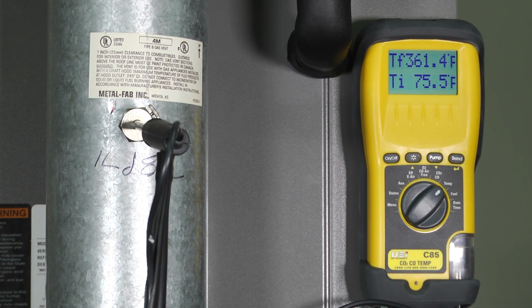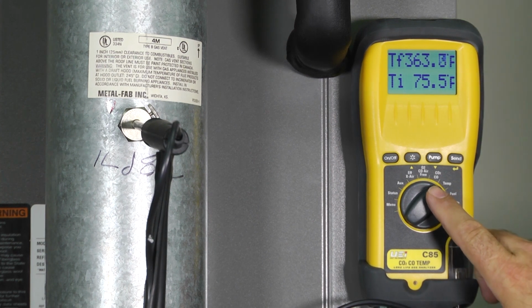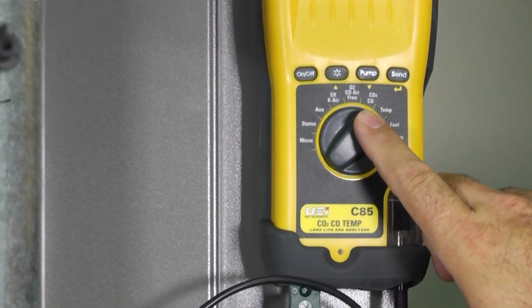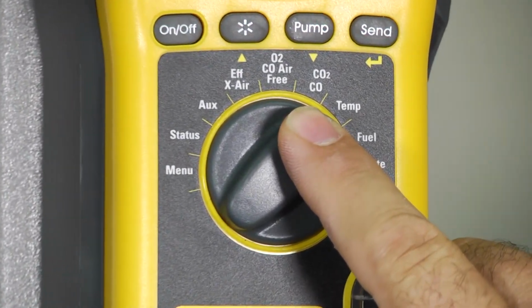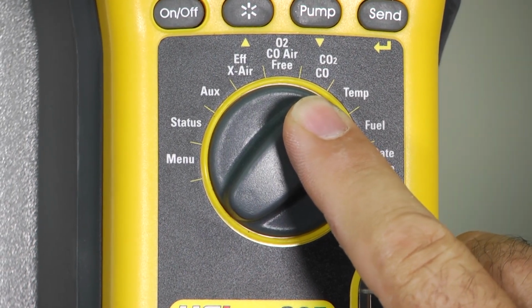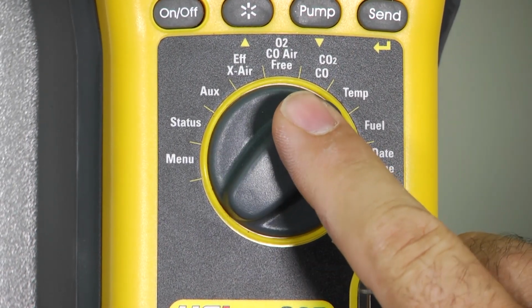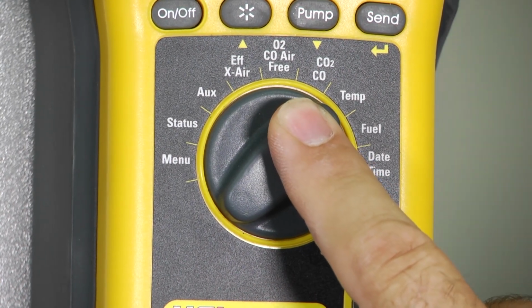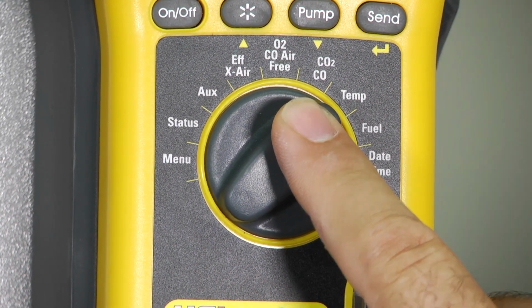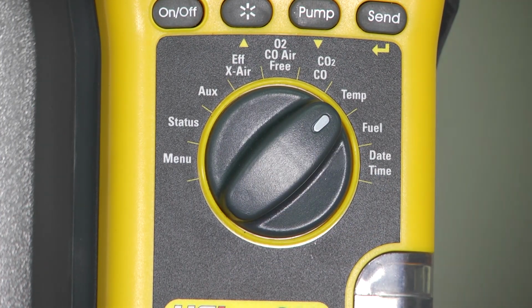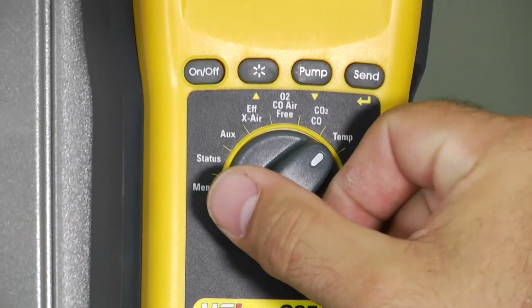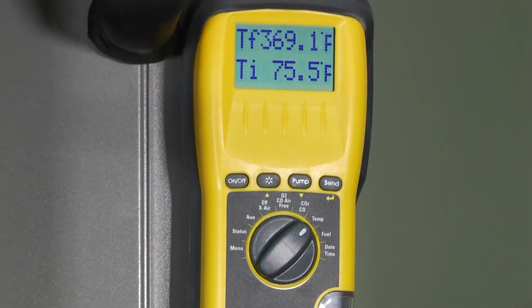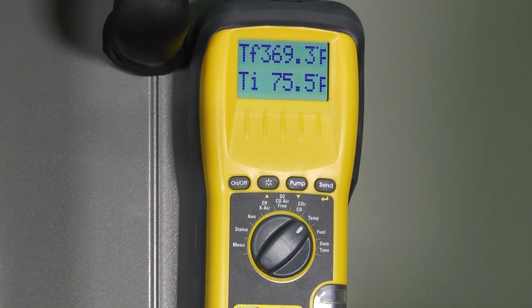So when we talk about air-free, if you can zoom in here on the front of our analyzer, you can see that it shows O2, CO, air-free. That means when I put my analyzer on CO air-free, it actually does a calculation inside to take out the excess air, so now I can see what my CO really is in my flue gases. Because it can be much higher than it first appears. So now I'm still starting to balance out. I'm running about 369 degrees, 370.